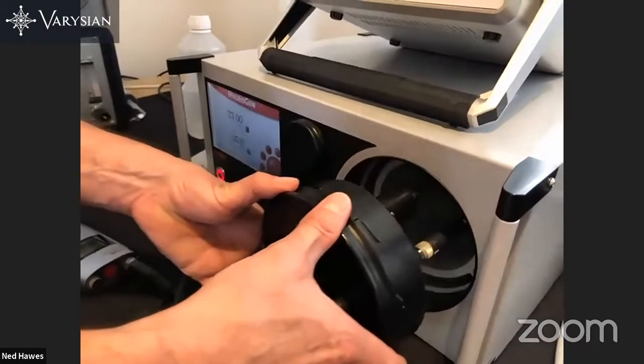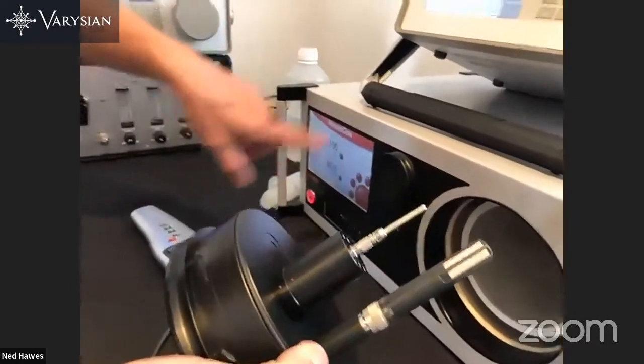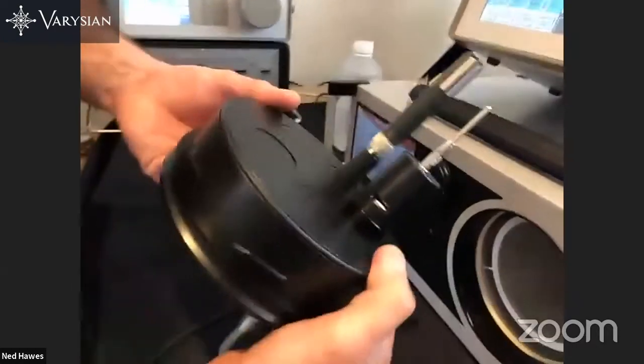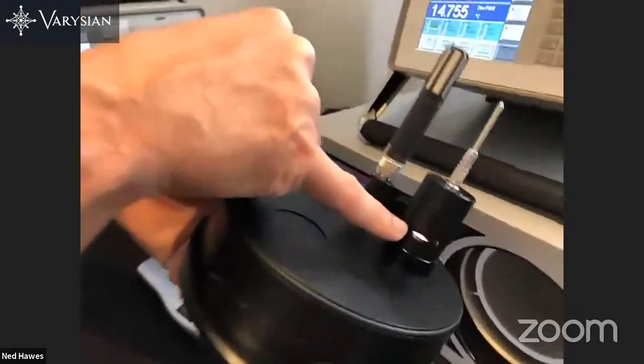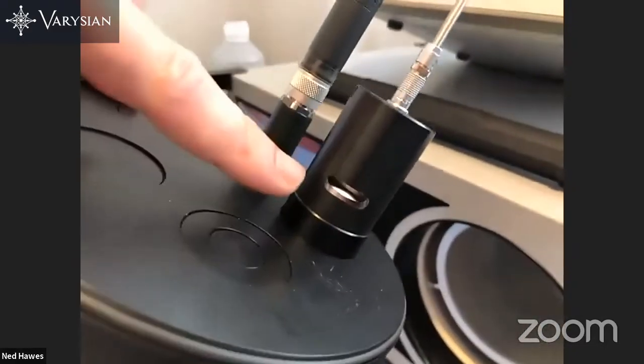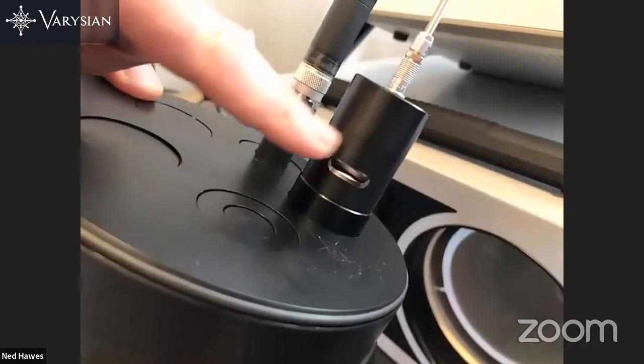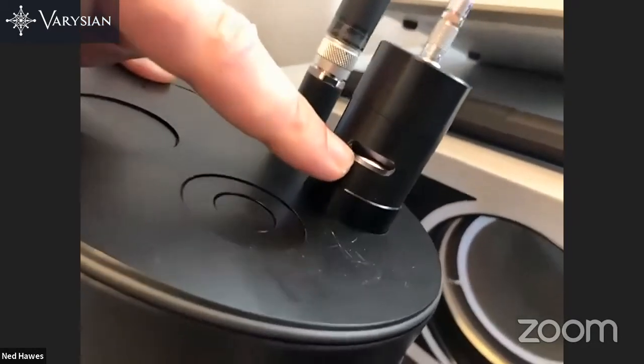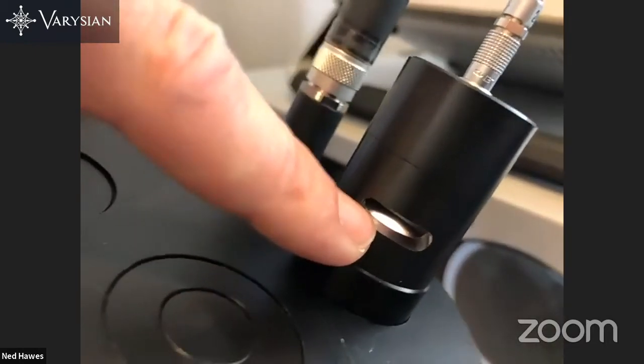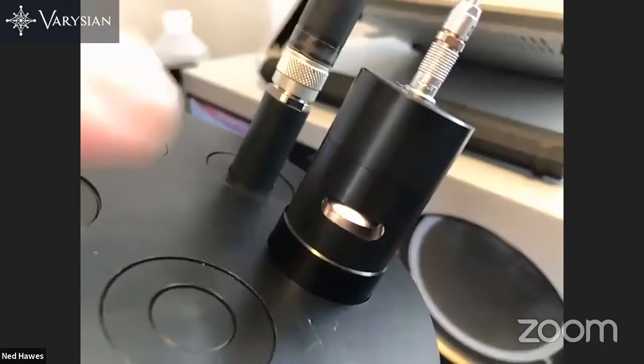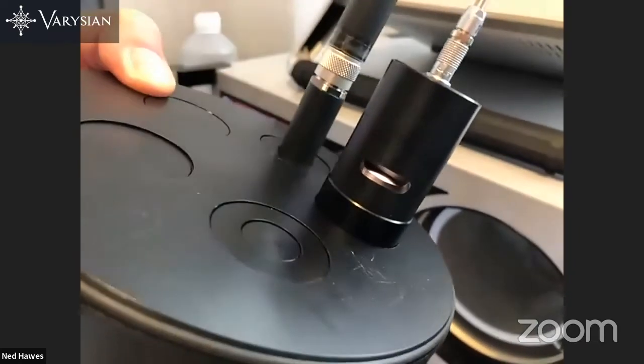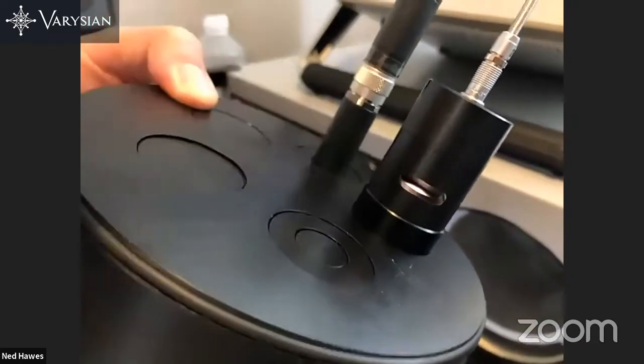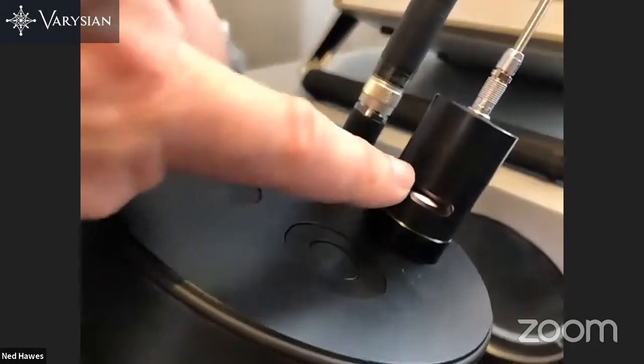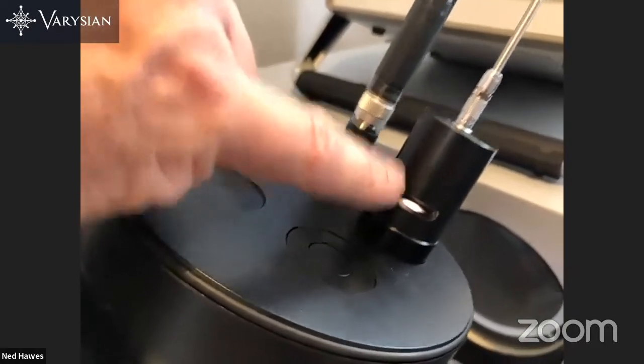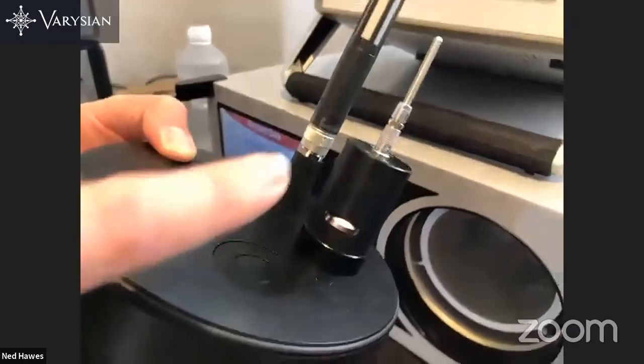What you have here is a mirror surface, lit by a diode and detected by a photodiode. It detects the point at which a dew or frost film forms on that mirror surface, and it measures the temperature at which that forms. That will be the dew point of the condition it's measuring.